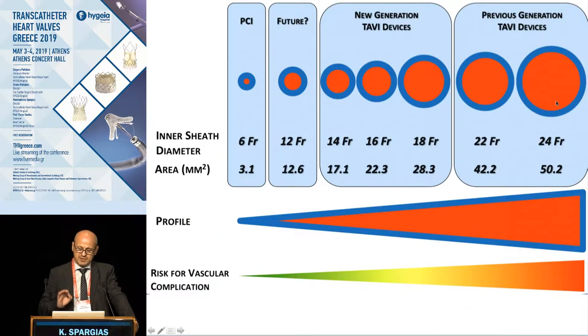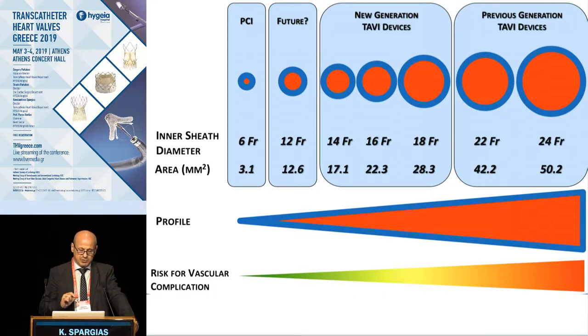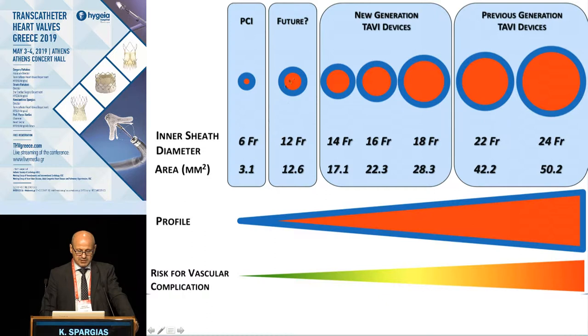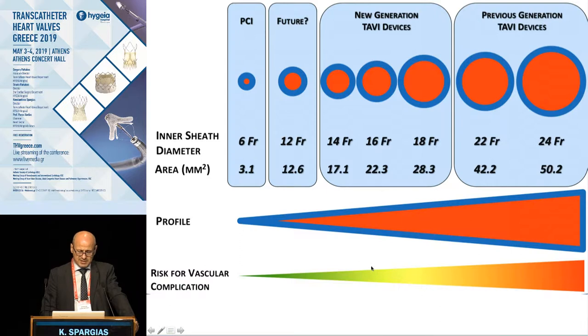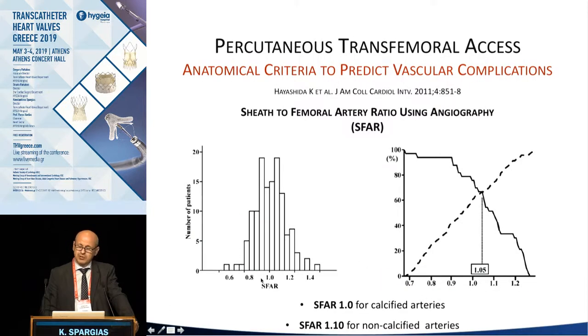We started from 24 French profiles to deliver our devices and are now down to 14 French. When we import these numbers, they are the inner diameters of the sheaths. To get the outer diameter, we add 3 to 4 French. To convert French to millimeters, remember that one millimeter equals 3 French. We hope and expect to achieve 12 French-compatible devices in the future, and as the profile of our devices goes down, the risk of complications also goes down.